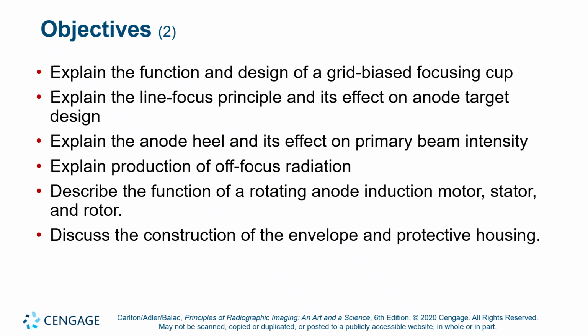The line focus principle allows us to spread out electron bombardments across the surface of the anode while maintaining a small effective focal spot. Okay, and we'll show you how we do it. Basically, it's the hypotenuse of the triangle for the bombardment zone versus the short side of the right triangle for the effective focal spot. Okay, but we'll get there.